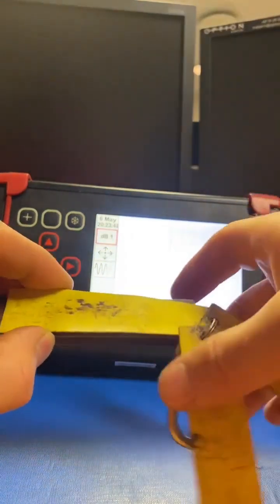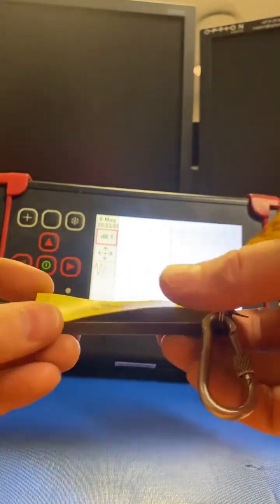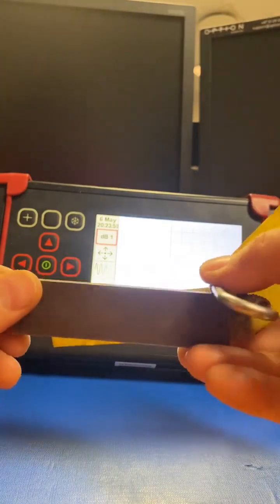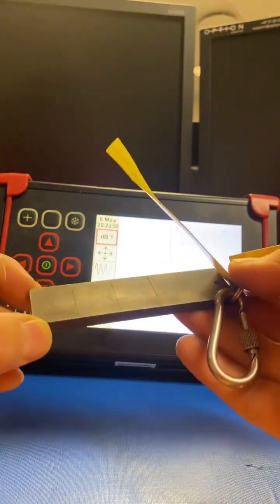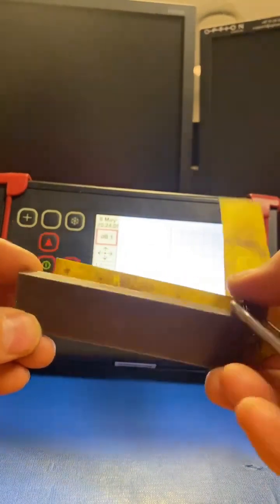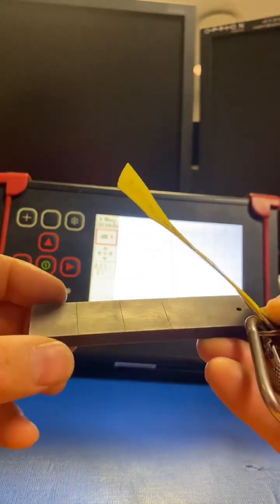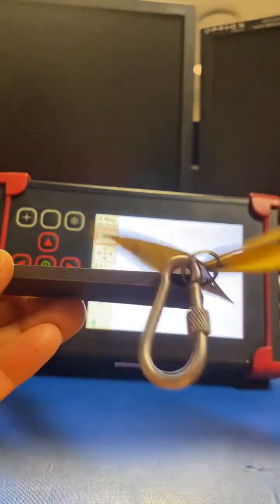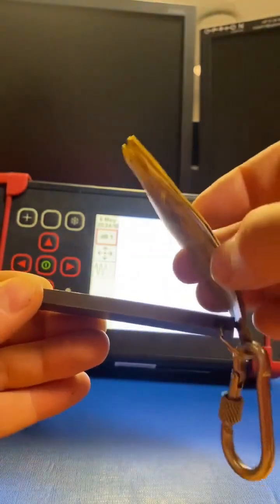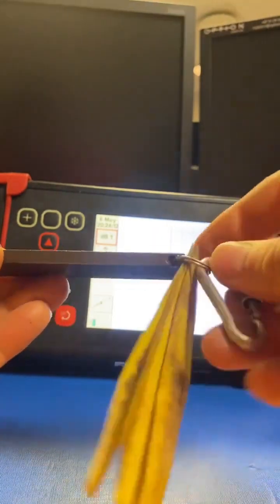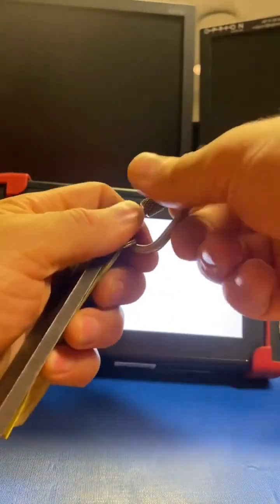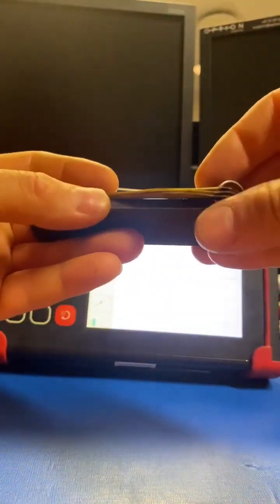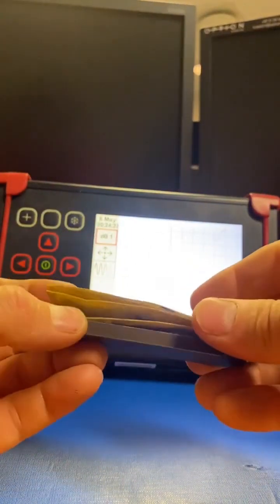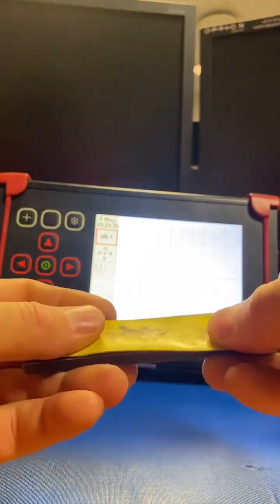Also, we're going to use a different type of calibration block. This is for carbon steel. Also, we have for stainless steel and for aluminum. You can find that this one has a little bit of corrosion. It means it's carbon steel. And here are the layers that imitate paint. One layer is 0.5 mil. We have 4 layers. It means we have 2 mil. Normally we use 1 layer, 0.5 mil.